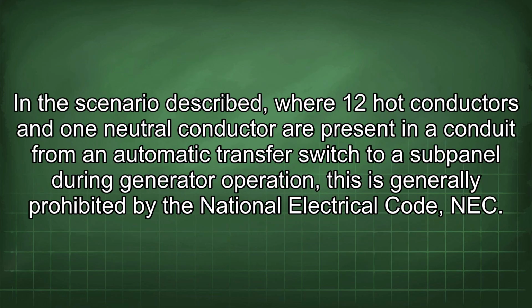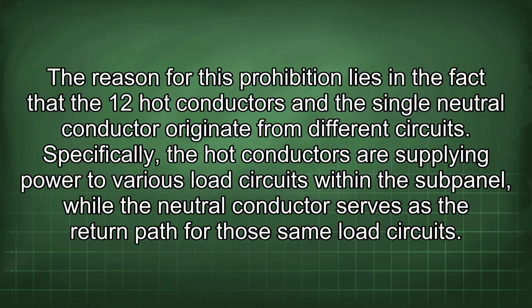In the scenario described, where 12 hot conductors and 1 neutral conductor are present in a conduit from an automatic transfer switch to a subpanel during generator operation, this is generally prohibited by the National Electrical Code, NEC. The reason for this prohibition lies in the fact that the 12 hot conductors and the single neutral conductor originate from different circuits. Specifically, the hot conductors are supplying power to various load circuits within the subpanel, while the neutral conductor serves as the return path for those same load circuits.